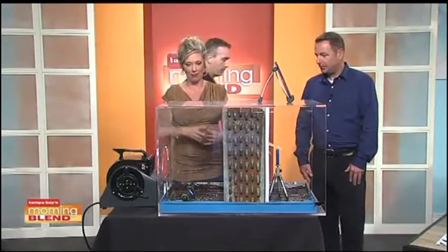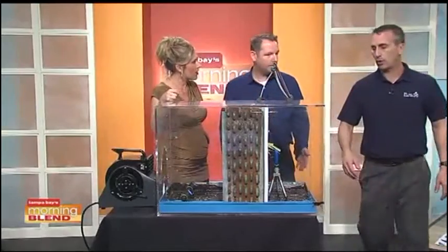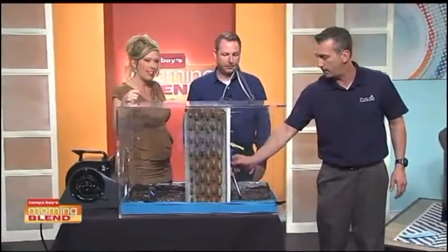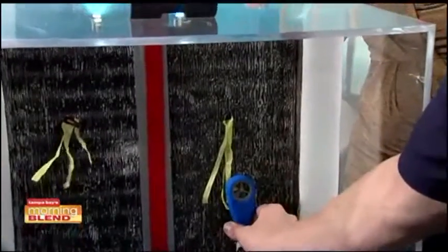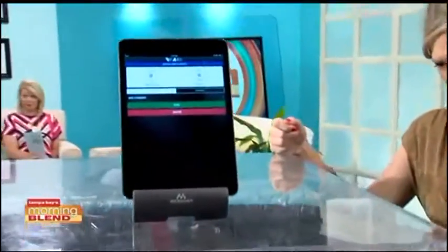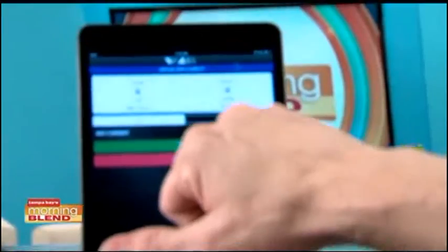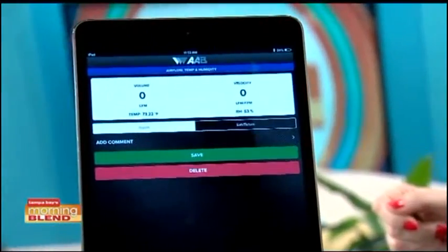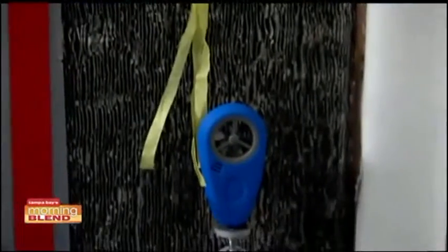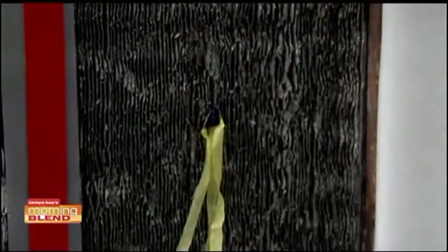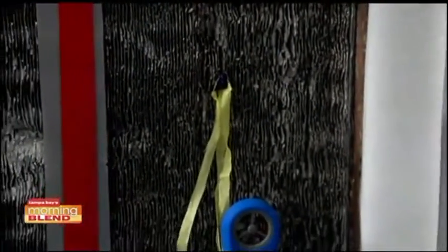Okay, now, this anemometer will show you the difference between a coil that's dirty, has not been cleaned correctly. Oof. And you can tell there's zero airflow going across the coil. Now, this is not just because of bad coil cleaning, but also because of insufficient filtration. So if the unit's not filtered properly, dirt's going to get into the coil and get impacted.